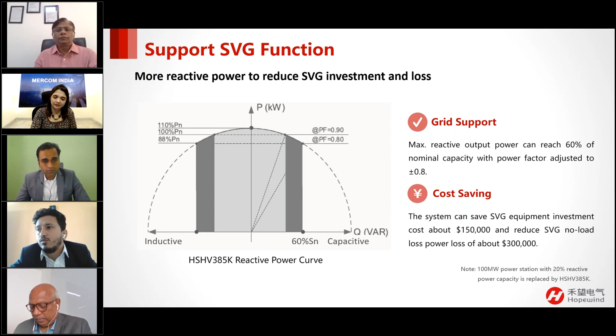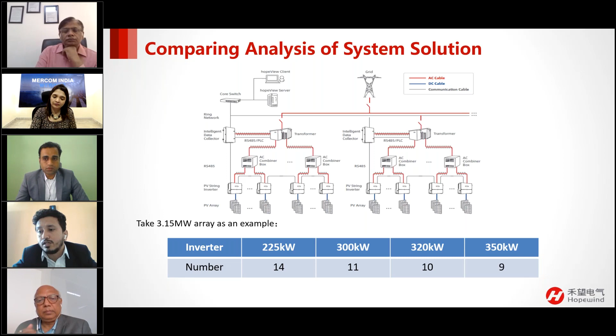Here is a comparison of different capacity inverters for an array of 3.15 megawatt. You can easily see the reduced number of units as the kilowatt rating of the inverter increases. For a 3.15 megawatt array, comparing 225 kilowatt and 350 kilowatt inverters, the unit cost is the same. So apart from inverter cost saving, there is savings in equipment cost, reduced BOS cost, reduced O&M cost, fewer units, and reduced LCOE as well.